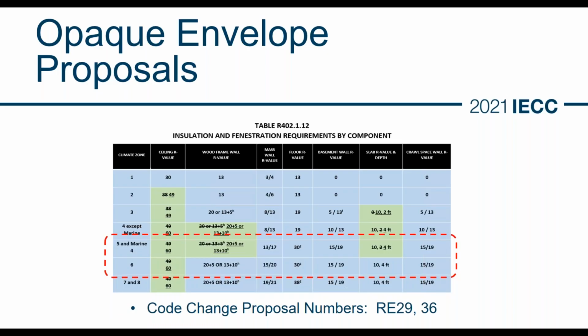So the first proposal I want to talk about is for the opaque envelope. This would require more insulation in wall systems, the ceiling assembly, and for slab on grade, deeper slab edge insulation. These are code change proposal numbers 49 and 36, or 29 and 36. These did not pass in Albuquerque, so public comments were submitted to try to get them in. Essentially, for the Northwest climate zones, we would be bumping up ceiling insulation from an R49 to an R60. And for wood frame walls, if you went prescriptive, you would be required to install continuous insulation. So if you went prescriptive for climate zone 5, there would be no cavity insulation only options using this table.